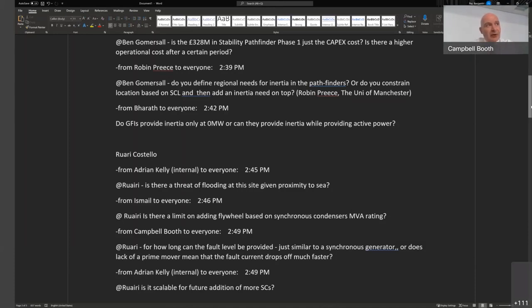I'm just wondering if there are differences. It's one thing to talk about short circuit level, but it's another thing to talk about how sustained it might be when the protection and the circuit breakers might not operate for tens of milliseconds. I don't know if it's a concern at all. I cannot imagine the envelope you're mentioning, so I might need time to think about my answer on that. Put it in the chat anyway. I was just interested, if there are lots of these in the system, does it change the make or break capacities, or how long a fault might be sustained?